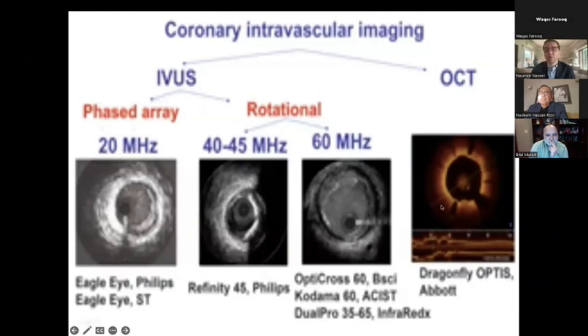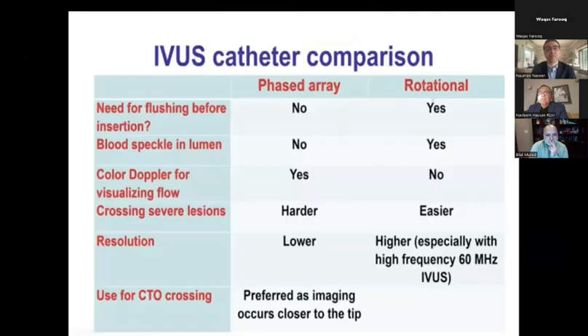And this is the OCT image with the even better resolution over here. So phased array versus rotational, if you were to buy, the rotational catheter is a better resolution, but there is blood speckle in the lumen, needs flushing before insertion. It is easier to cross. It's less bulky than the phased array catheter. Resolution is better. But for CTO crossing, because it is closer to the tip, this phased array catheter may be preferred only in that scenario.